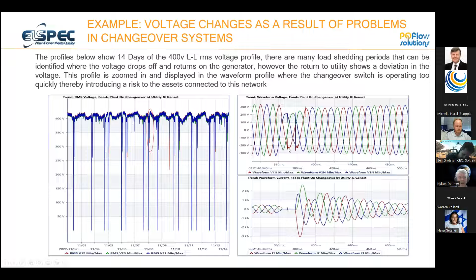What we found when we opened up, so we've gone from 14 days to literally cycles on the right-hand side here, was that the changeover was happening far too quickly from the generator back to the network. If you look at the blue phase voltage, so the current drops off on the bottom, you can see that, but the blue phase voltage on the changeover changes to the green. So look at that. Then the green changes to the blue. Look at that transition over there. So now you can imagine the mechanical interaction required, and hence we have almost a 2.5 kA peak on the current waveform as this network tries to integrate and synchronize with the new phase group when connected to the utility. So this is where high resolution data benefits you from the start.